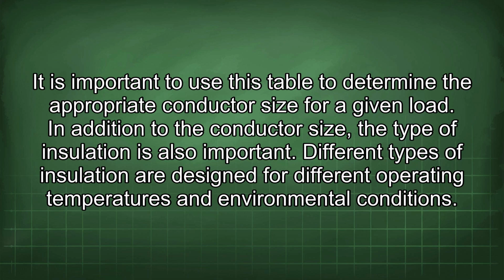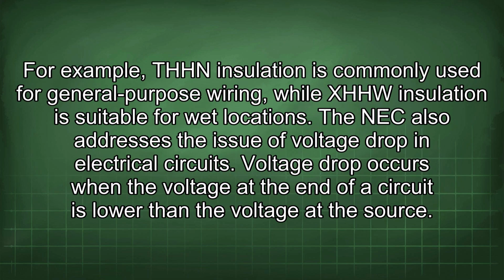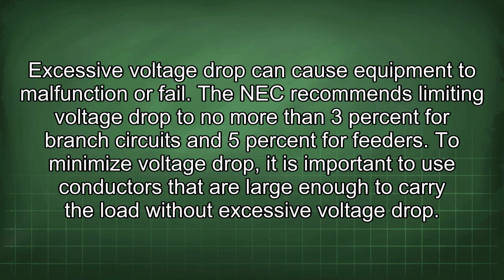load. In addition to the conductor size, the type of insulation is also important. Different types of insulation are designed for different operating temperatures and environmental conditions. For example, THHN insulation is commonly used for general-purpose wiring, while XHHW insulation is suitable for wet locations. The NEC also addresses the issue of voltage drop in electrical circuits. Voltage drop occurs when the voltage at the end of a circuit is lower than the voltage at the source. Excessive voltage drop can cause equipment to malfunction or fail. The NEC recommends limiting voltage drop to no more than 3% for branch circuits and 5% for feeders.